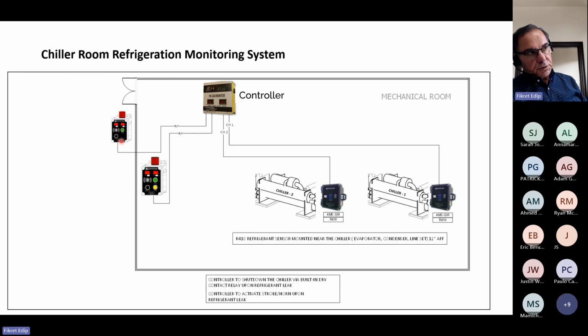But you pay attention, the strobe outside does not have a stop push button. The stop push button is only on the one inside. Why? To comply with the B52 code, CSA B52 code. So somebody accidentally will not go outside, shut off the alarm, and then you harm people inside.